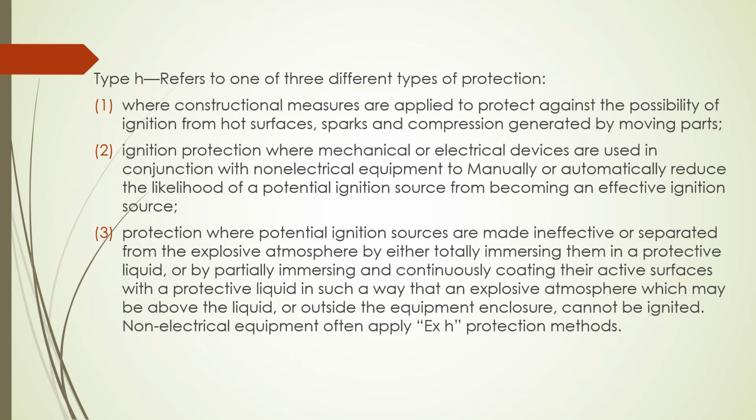Protection, where potential ignition sources are made ineffective or separated from the explosive atmosphere by either totally immersing them in a protective liquid or by partially immersing them while continuously coating their active surfaces with a protective liquid, in such a way that an explosive atmosphere which may be above the liquid or outside the equipment enclosure cannot be ignited. Non-electrical equipment often applies "Ex h" protection methods.